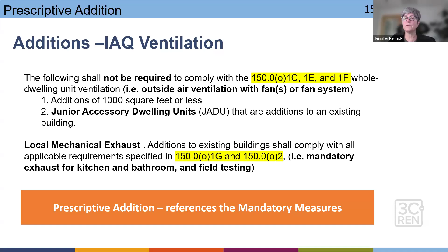And if you have a junior accessory dwelling unit, or JADU, so in other words, it's essentially an alteration, we call it a remodel because JADUs are interior to the main residence, then the IAQ ventilation isn't triggered. But you still have to comply with the mandatory exhaust requirements for your new bathroom and new kitchen, for example. And then those ventilation requirements still continue to be based on ASHRAE 62.2. And if you do have a project that triggers the outside air ventilation requirements, then they will be field verified by your ECC rater. And for your bathrooms and kitchens, for the required exhaust ventilation, the language for how you meet those requirements has been updated.